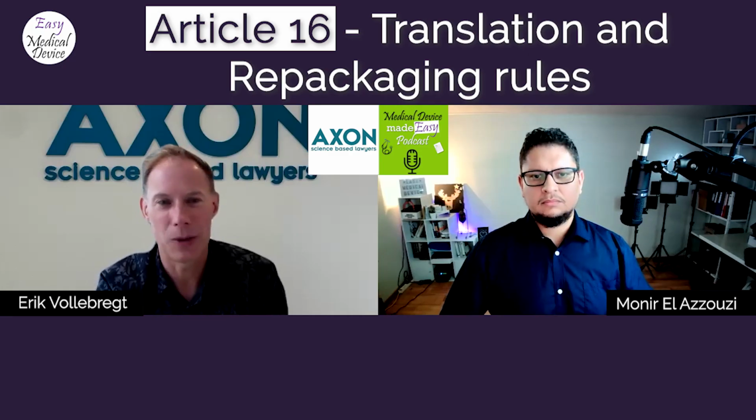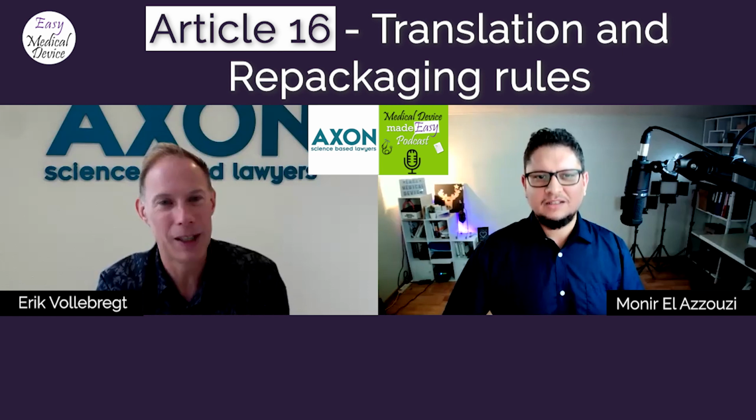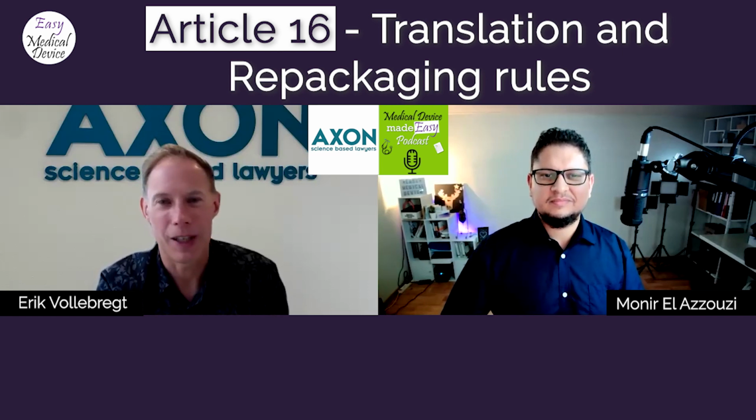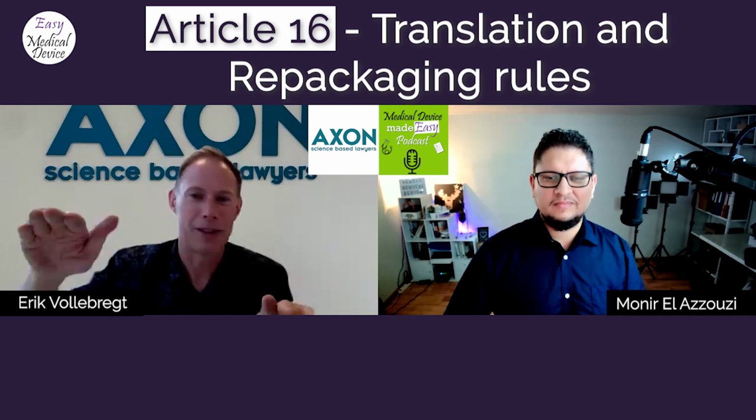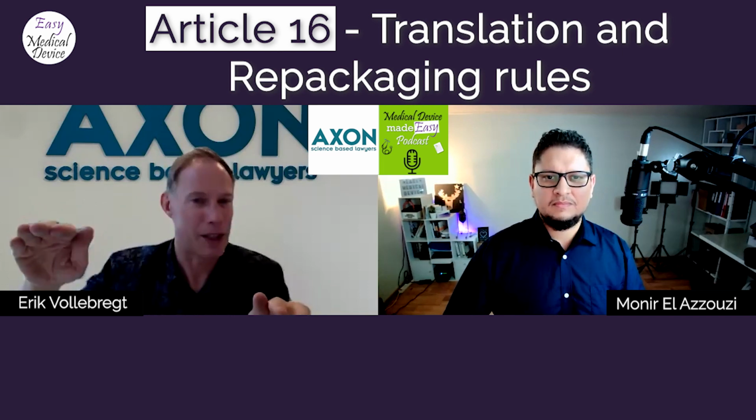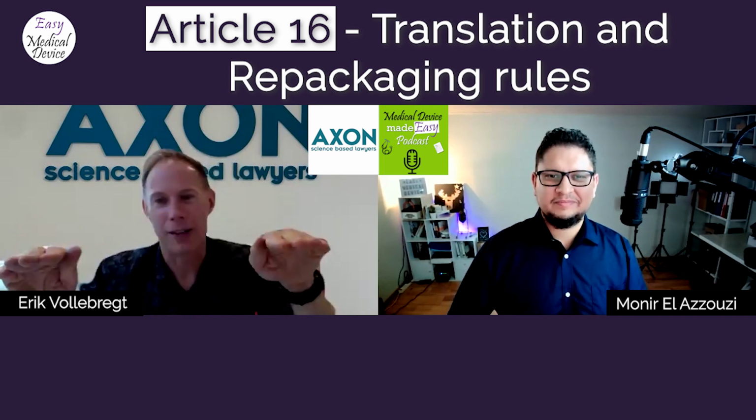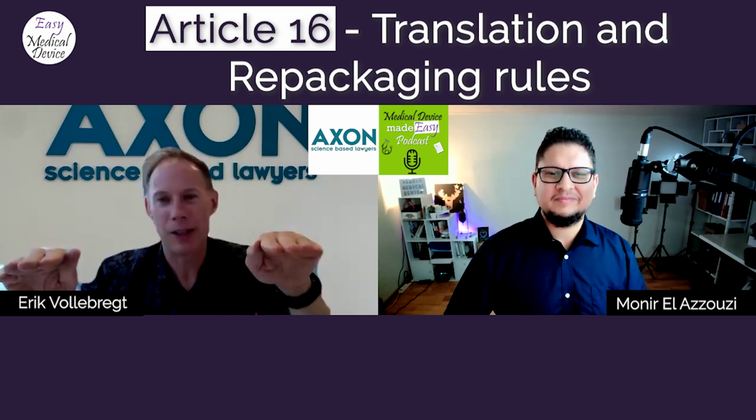Because it's not conformity assessment, we will just go to our local ISO 13485 certification body. Exactly. And they can certify us for this activity, of which I said at the time, well, that's probably not what it says in the MDR and the IVDR, because the MDR and the IVDR is a bit on the fence. On the one hand, they say it's not conformity assessment. On the other hand, they say you do need a notified body.